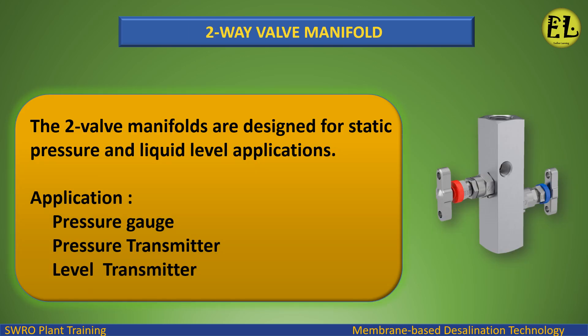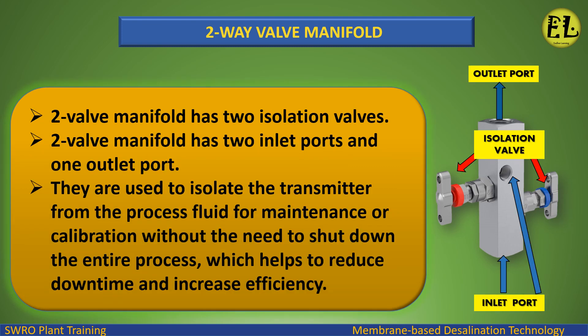Two-way valve manifold: the two-valve manifolds are designed for static pressure and liquid level applications. Applications include pressure gauge, pressure transmitter, and level transmitter. A two-valve manifold has two isolation valves, two inlet ports, and one outlet port. They are used to isolate the transmitter from the process fluid for maintenance or calibration without the need to shut down the entire process, which helps to reduce downtime and increase efficiency.